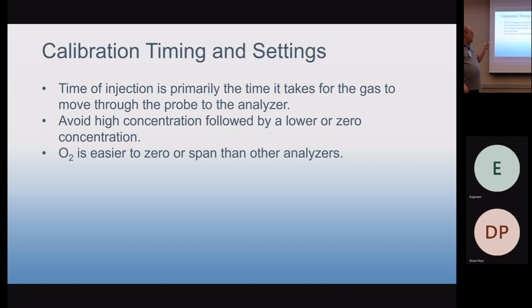And on most of those systems, we start with the O2 span, and that zeros the CO and the NOx analyzer. But unfortunately, we are ending with NOx or we are ending with CO. So a lot of our engineers have started putting what we call a purge valve into the system, where we're literally going back to the instrument air at the end of cal. We turn that purge valve on for a minute or two and blow the system out with ambient air and get rid of the residual gases. If you don't have those purge valves available in your system, you might think about trying to figure out how to put them in there. We'll be more than happy to help you program them into the calibration.